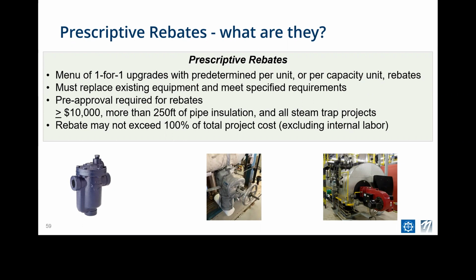So just some pictures of some common things here. Steam trap on the left, an insulated removable jacket on a bonnet for a steam valve that normally is not insulated. We pay huge money for these. They're just as effective as pipe insulation, but they last for 20 years. And when you have to go exercise that valve or change it or fix it, take it off with the Velcro and the rings, put it on the floor, put it back on when you're done. It'll last for 20 years.